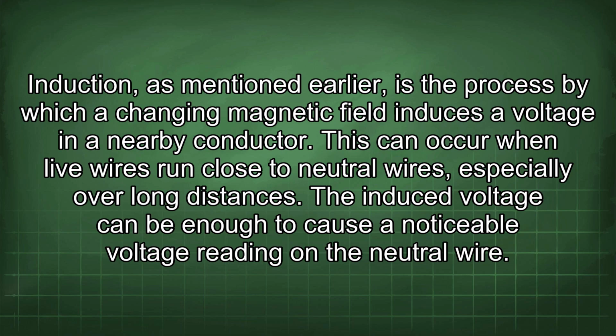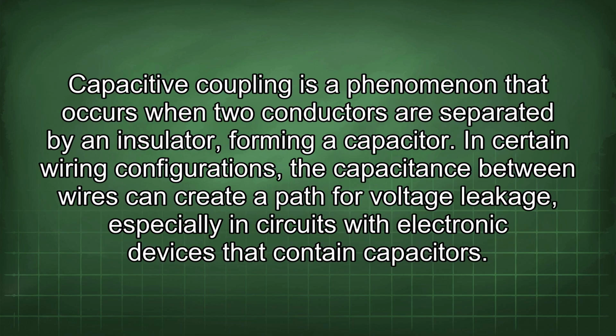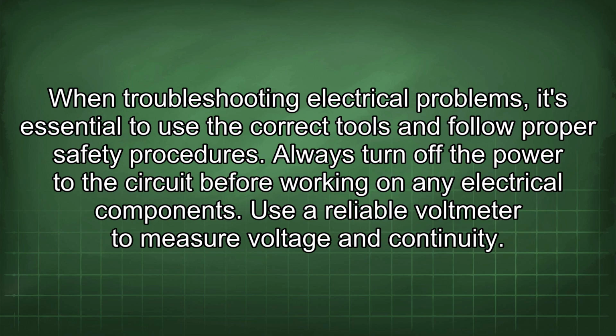Induction, as mentioned earlier, is the process by which a changing magnetic field induces a voltage in a nearby conductor. This can occur when live wires run close to neutral wires, especially over long distances. The induced voltage can be enough to cause a noticeable voltage reading on the neutral wire. Capacitive coupling is a phenomenon that occurs when two conductors are separated by an insulator, forming a capacitor. In certain wiring configurations, the capacitance between wires can create a path for voltage leakage, especially in circuits with electronic devices that contain capacitors. When troubleshooting electrical problems, it's essential to use the correct tools and follow proper safety procedures.